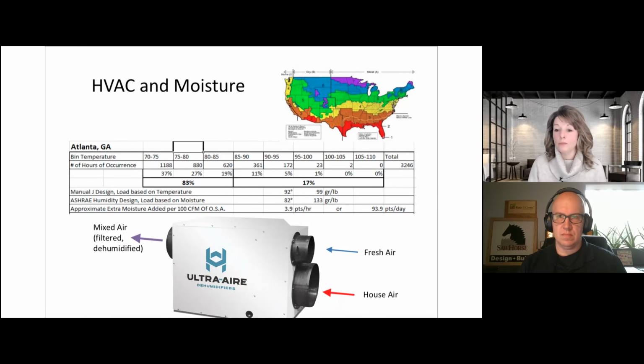So in humid climates, we definitely want to think about how we're going to do some makeup air for our exhaust. And exhaust is bath fans, kitchen hoods, and we've got dryers going. And if we've got all three of those going at one time, we've got a significant amount of makeup air trying to get in the house from somewhere. And so supply ventilation typically can help that out a little bit.